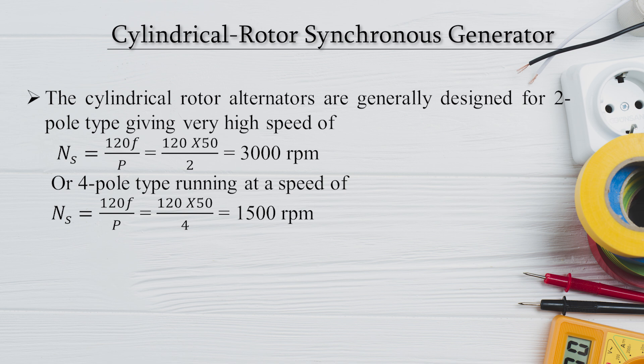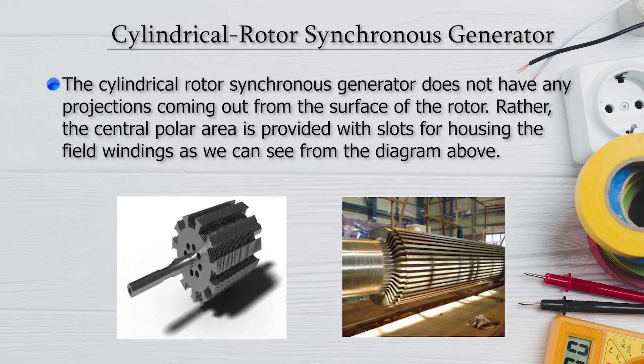We would not use the salient pole type of generators for high speed. The cylindrical rotor synchronous generator does not have any projections coming out from the surface of the rotor, which helps it be used for high speeds. Otherwise, if the poles are projected out, you face wind resistance there, resulting in a lot of losses.